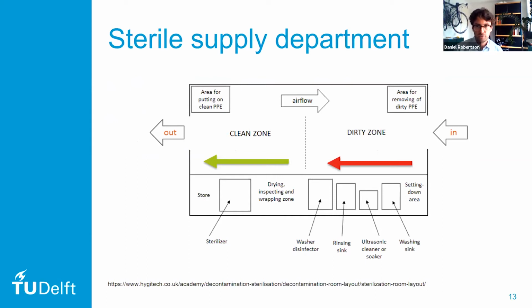Now, reprocessing ideally needs to be done in a dedicated space. By working in a dedicated space, it doesn't only improve patient safety, but also the working conditions for the staff. Now, even smaller hospitals can take measures to improve the location where the instruments are sterilized. And one of the most important aspects about this location is that it should be a space where instruments can be processed in one direction. So the dirty instruments get brought in after surgery, and in one direction they move through the whole space until they are clean and sterilized, and then they're moved away. Now, by working in one direction, it prevents cross-contamination of the instruments that were already sterilized. And by having a dedicated space, it also provides an environment where the staff can take the time to properly inspect the devices.